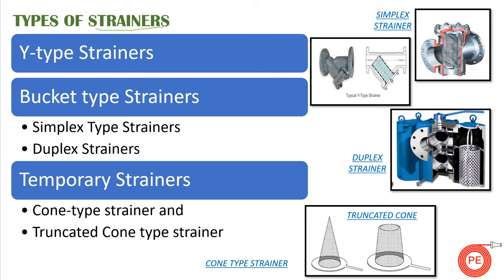Strainers are basically of three types. The first is the Y-type strainer, one of the most common strainers you would see near pumps. It forms a horizontal Y shape, with a filter placed inside. Flow moves through one side, passes through the filter, and exits from the outlet. The second is the bucket type strainer, which has two subtypes: simplex and duplex strainers.